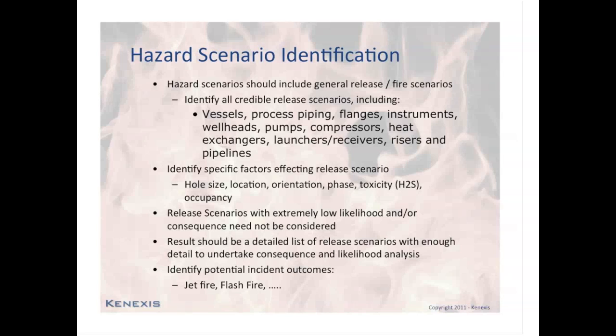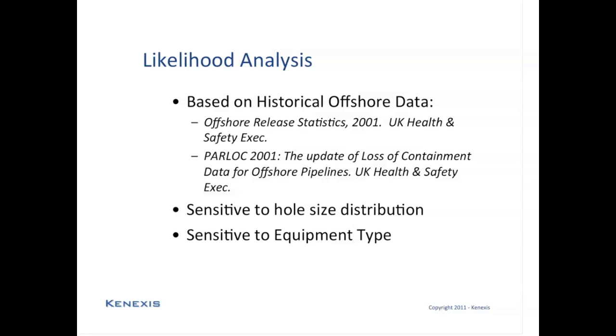And for each one of the release scenarios, we're going to identify a list of the potential incident outcomes, such as jet fires, flash fires, vapor cloud fires, and pool fires. After the consequence analysis has been performed, a likelihood analysis will need to be performed. As mentioned previously, the likelihood analysis is not performed using predictive techniques that are based on knowledge of the scenario by which the loss of containment occurs. Instead, a statistical probabilistic inference technique is going to be used to estimate future release rates or loss of containment rates based on historical data of which these releases have occurred.